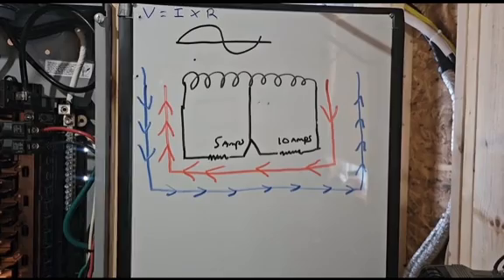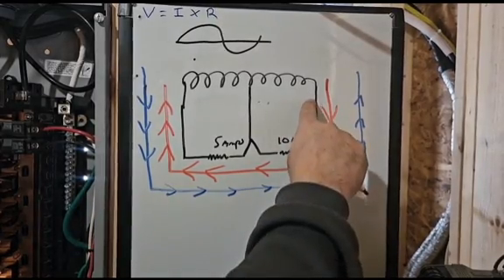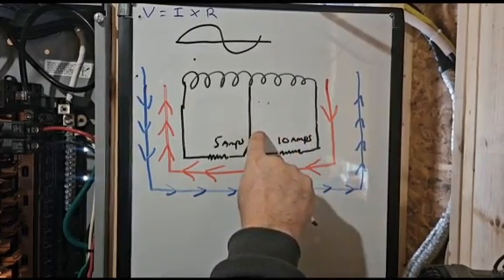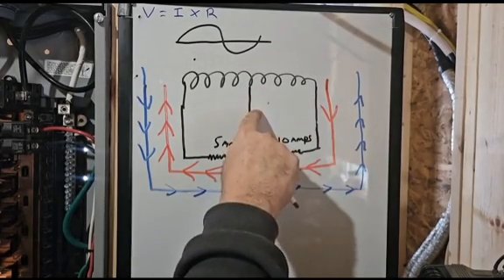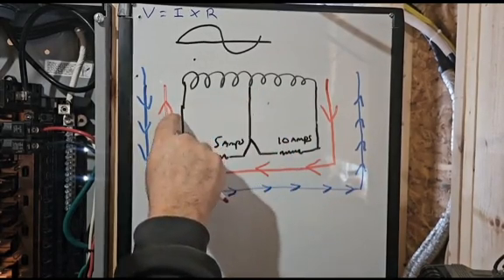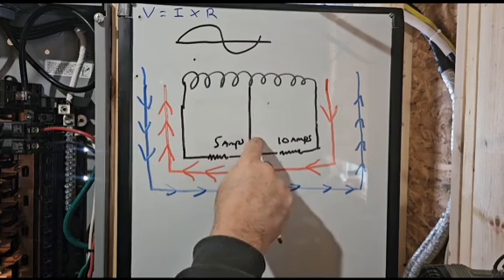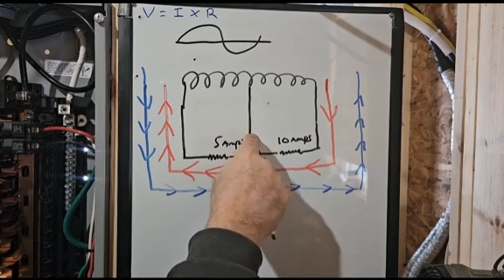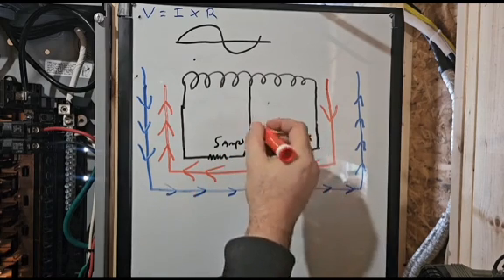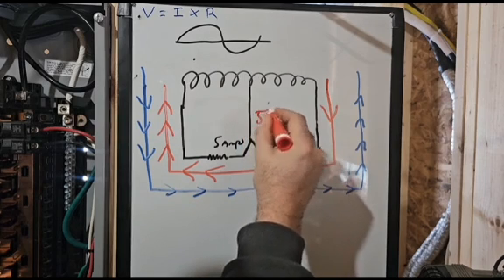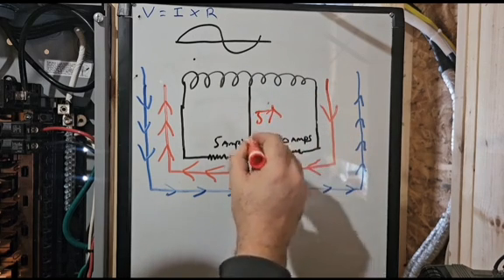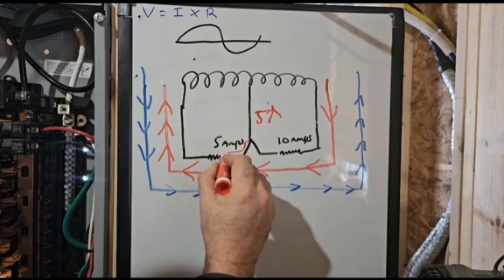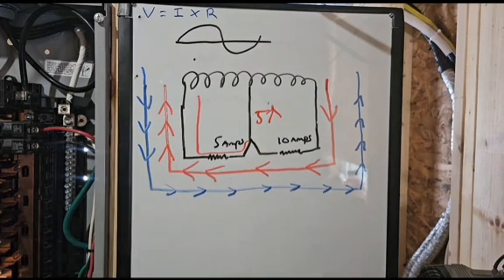Now let's follow the amps. When the red path is being used, the 10 amps leave here and come here. This has less potential than that leg. This is the neutral, but this has even less potential. Because Ohm's Law kicks in, this is only going to be a 5 amp load. The extra 5 amps that this leg brought up goes back on the neutral, and then the other 5 amps goes back that way. That's when the red is running.